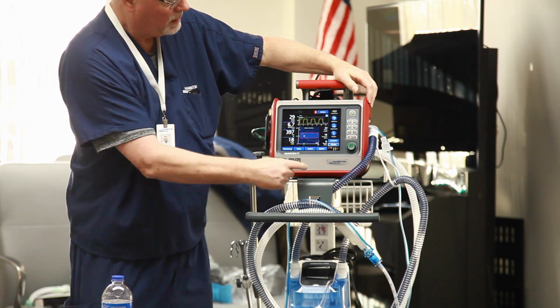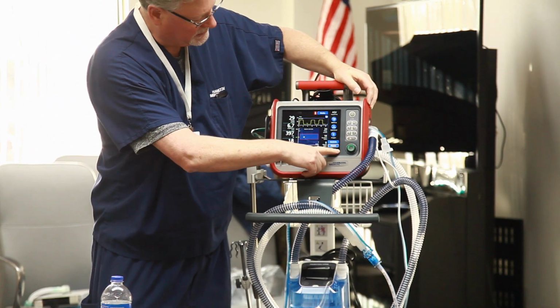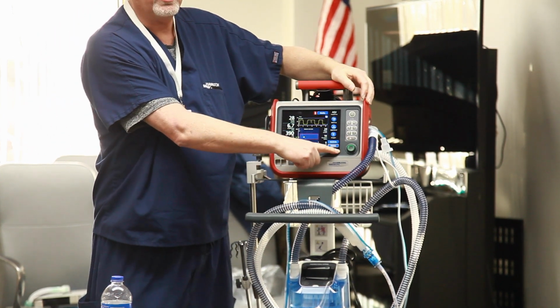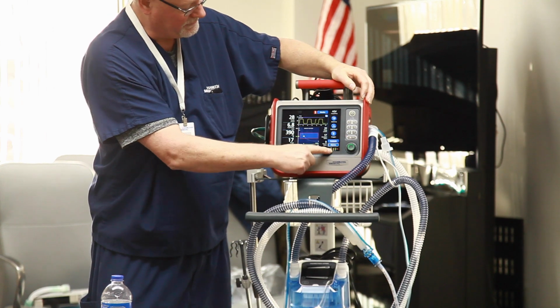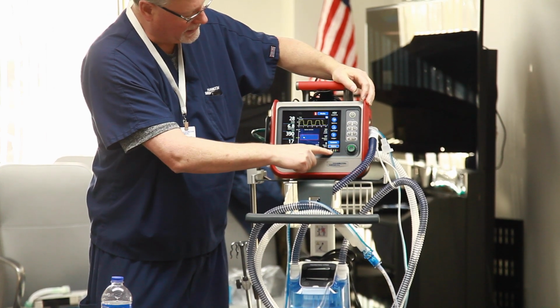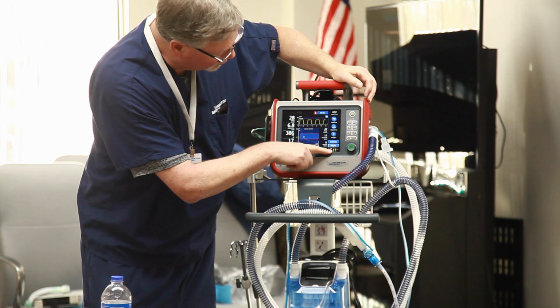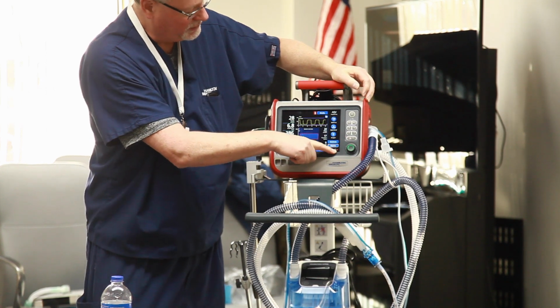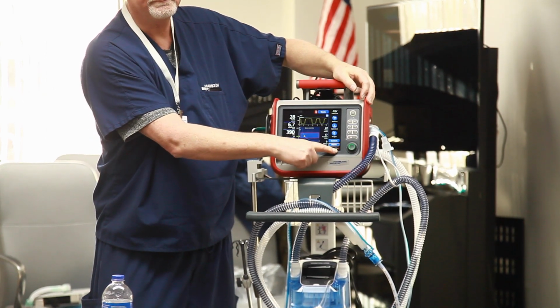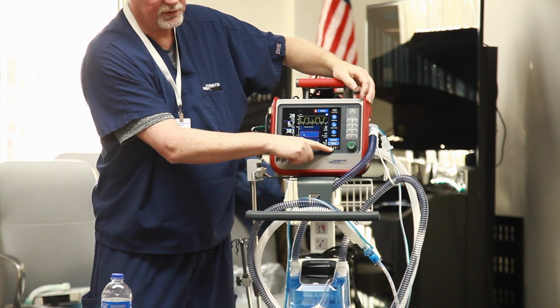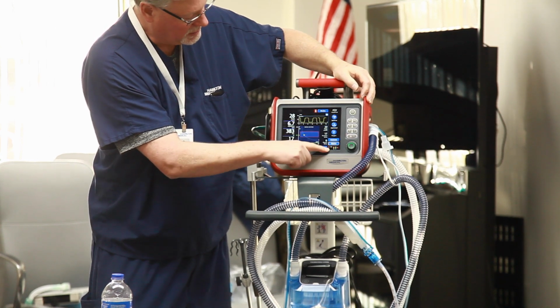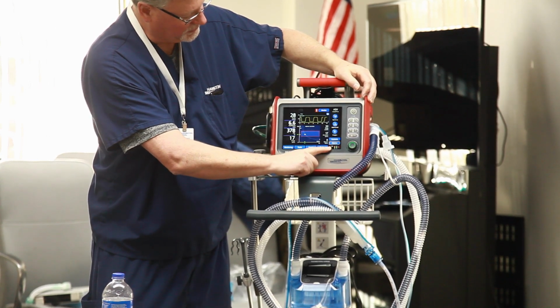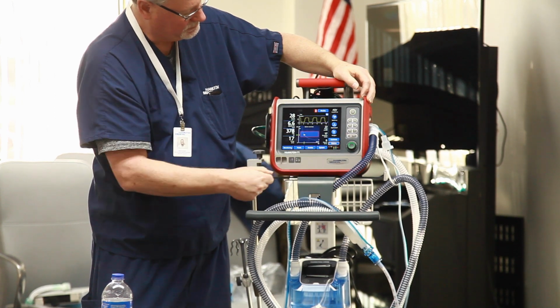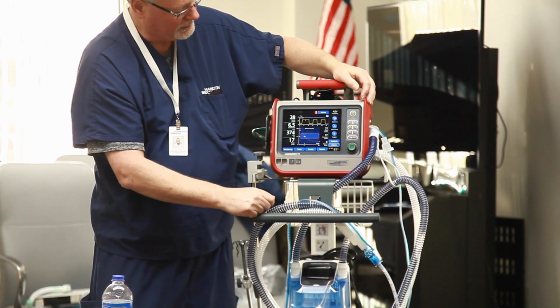Okay. Right here it tells me I'm not plugged in. That X would not be there where the power cord is if I was plugged in. I've got two batteries here, battery 1 and battery 2. Battery 2 must be about depleted, so it started on battery 1. All red here, so that tells you it needs to get charged. Right here is my alarm silence that I pushed, 2 minutes. You'll see the LED is on there.